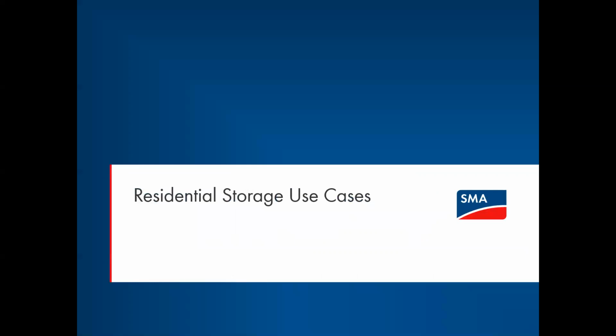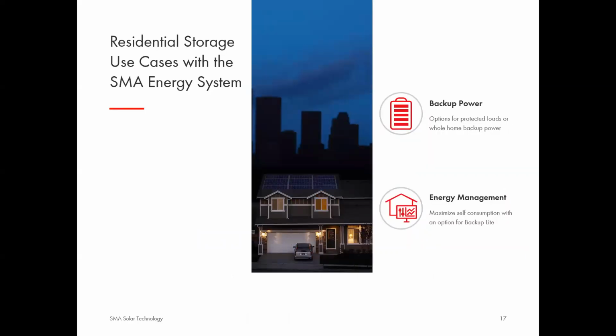So speaking of those primary use cases for energy storage, we like to describe them in two different high-level categories. There's the backup power use case, where we have options for backing up a protected loads panel or even an entire home, using the main service panel as the backed up load panel. And then the second use case is energy management. These are really the grid-tied use cases where you're trying to maximize your self-consumption.